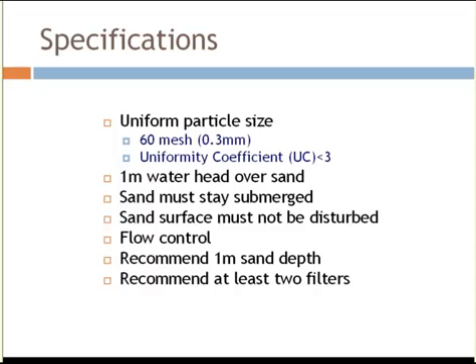Recommendations are for a sand depth of about one meter, and that at least two filters be installed. The reason for these two recommendations is that as the sand plugs — as the schmutzdecke becomes so thickened that it restricts flow — the filter will have to be taken out of operation. About a half inch to one inch of the top surface layer of sand needs to be removed, and then the filter can be returned to operation. While one filter is being maintained, the other filter can remain operational.